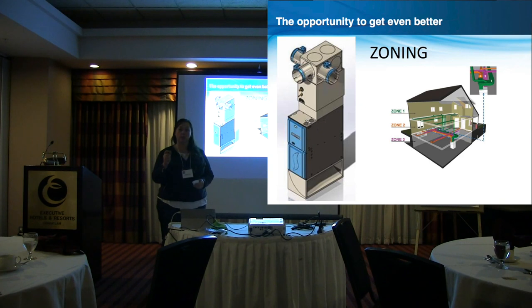You don't want to get into a situation where you are putting a traditional two-stage furnace on there, because then you're going to have a high velocity system. And I think high velocity systems aren't bad, they just have a really bad reputation, and it's more so because of the inconsistency in installation, right? It's gotten a bad rap from cracked drywall, toupees flying off heads, and curtains flying off windows, right? Or walls. Some builders do high velocity really well, and other ones just can't get it right. So fundamentally, the builder said, we don't want high velocity systems anymore. And the noise probably is the biggest thing, I would say.